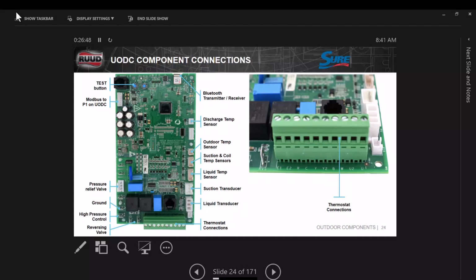Okay, so if you had your phone opened up to the diagnostic app on this thing, you could actually see the pressures the unit's running on your phone or on the EcoNet controller, whichever one you have hooked up, which I think is pretty cool, right? You can tell what your subcool, your superheat is all right there just by looking at this. Because we have the transducers and we have also the sensors, the thermistors, for both liquid line and the coil temperature on the suction line. We have an outdoor temperature sensor that senses the outdoor temperature and a discharge line sensor that senses the discharge line temperature. And right there at the top right of the board is the Bluetooth transmitter.